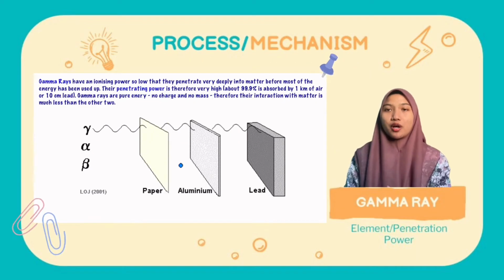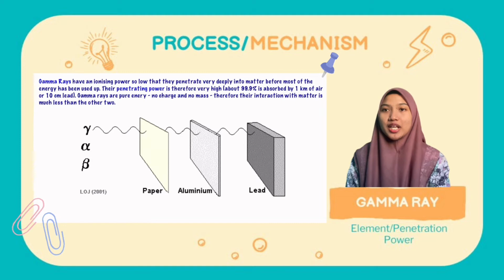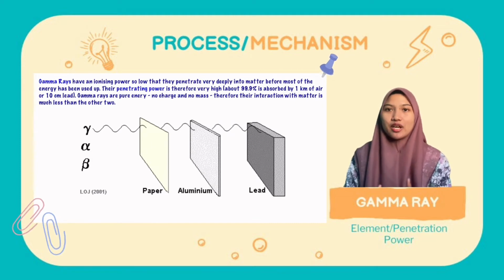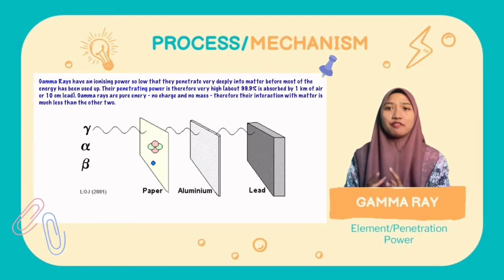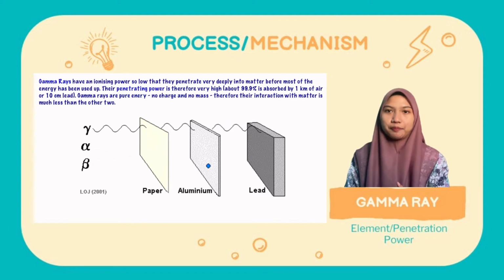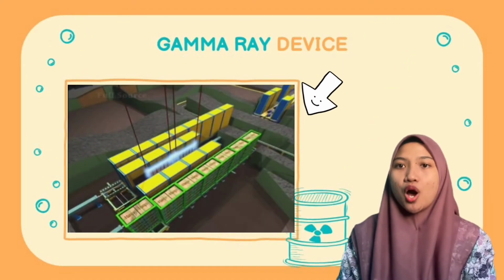The process or mechanism of the gamma ray: the radiation element of gamma ray is emitting gamma rays, which are photons. The characteristics of photons are that they create the ionization event needed for sterilization, and second, they can penetrate deeply into the product because of having a very short wavelength. This makes them an excellent sterilizing agent. This is an example of the overview of the gamma ray.